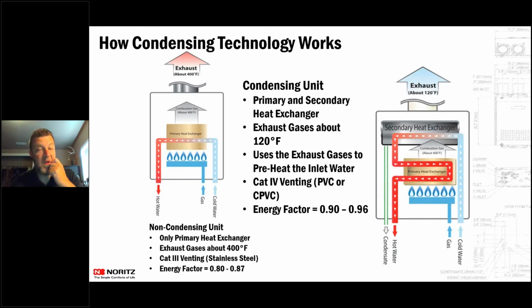It was really a pain to vent out one of those old non-condensing units. So with condensing, you can see there is a primary and a secondary heat exchanger. The way this works with a condensing tankless water heater, which is 99% of what we sell here in Utah, the cold water comes in and goes to the secondary heat exchanger first, because we have the flue gases that are actually going through that secondary heat exchanger.